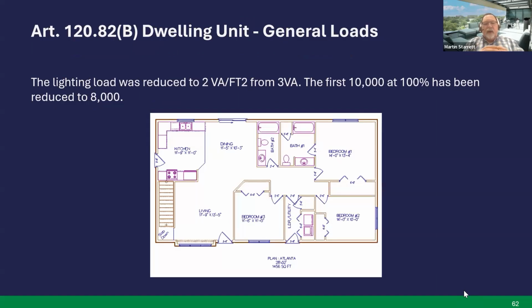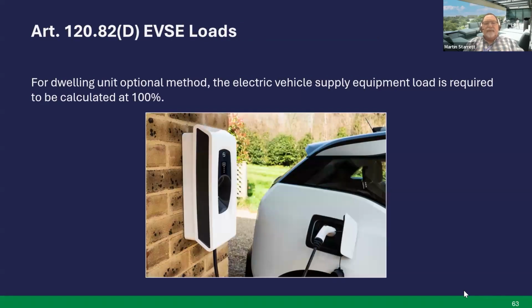Dwelling units general loads, 120.82B. Again, the lighting load was reduced to 2 VA from 3 VA, and there's been a change in the demand factor. The first 10,000 at 100% has now been reduced to 8,000. So the first 8,000 will now be factored in at 100%, and the remainder, I believe, is at 40%. Next slide.